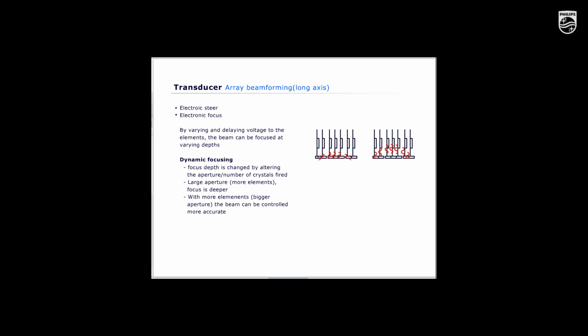When voltage pulses are applied in rapid progression from left to right, one ultrasound pulse is produced that is directed to the right. A similar pulse can be produced and directed to the left as well. A curve in the phase delay pattern results in focusing the pulse. A greater curve delay pattern, with longer time delays between the elements, moves the focus closer to the transducer. Conversely, shorter delays move the focus deeper. The more elements are used, the bigger the aperture, and the better the beam can be controlled.